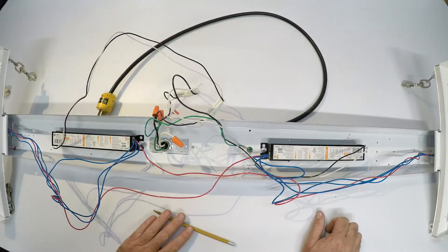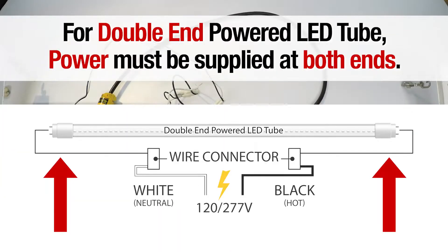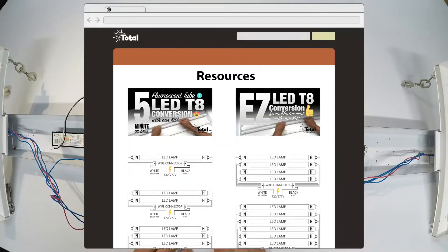The end result and the end goal is on a double-ended LED tube, we need to supply power to both ends. One end is hot and one end is neutral. We have all kinds of drawings and diagrams on our website so you can see what I mean.